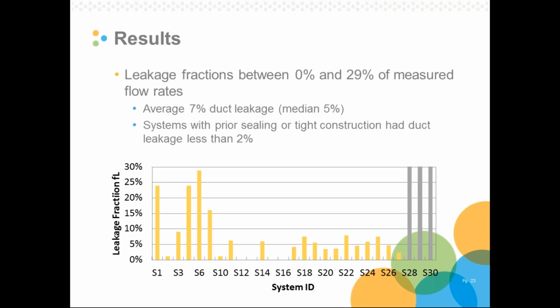And the numbers are pretty straightforward. Here's what we found. We measured a big range in leakage fractions. Again, leakage fraction is the percentage of air that's not reaching the final destination. And those numbers are between 0 and 29%. So we found ducts that were nearly airtight with respect to the ability of our research equipment, and ducts that were incredibly leaky at 29%. Our average duct leakage was about 7%, and the median leakage was 5%.